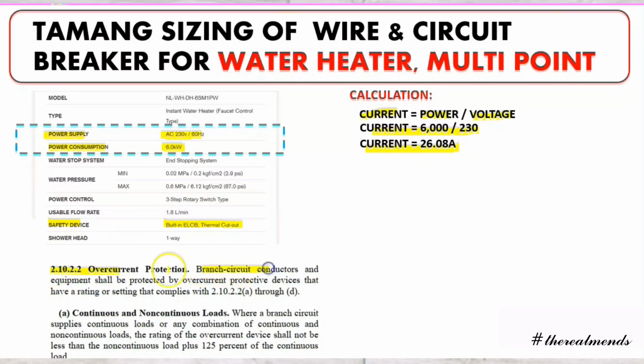Refer to the PEC for the overcurrent protection, 2.10.2.2. Our branch circuits and conductors shall be protected by the overcurrent device having a rating or setting that complies with 2.10.2.2a, continuous or non-continuous loads. A continuous load operates for 3 hours or more. So assuming our water heater is used 5 to 6 hours or more. Where a branch circuit supplies continuous or any combination of those loads, the rating of the overcurrent device shall not be less than the non-continuous load plus 125% of the continuous load. So assuming our water heater is a continuous load, we have to multiply by the factor of 125%.